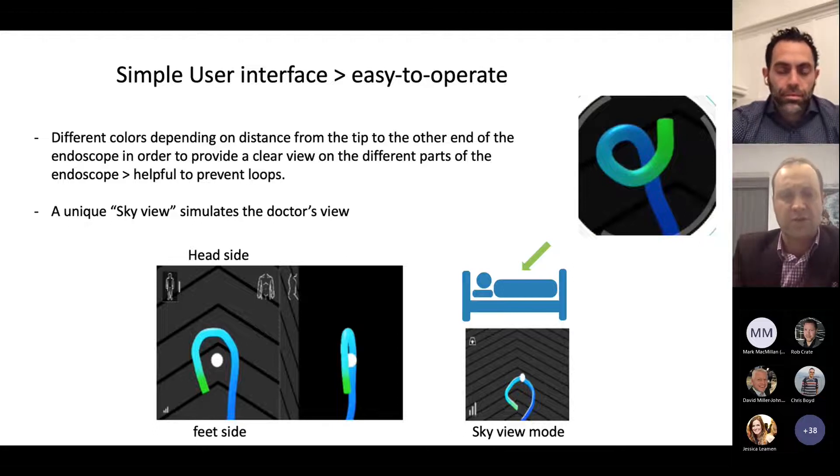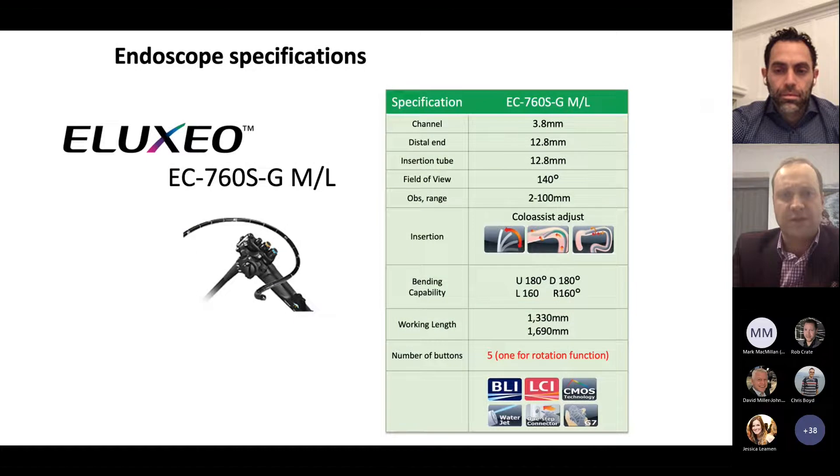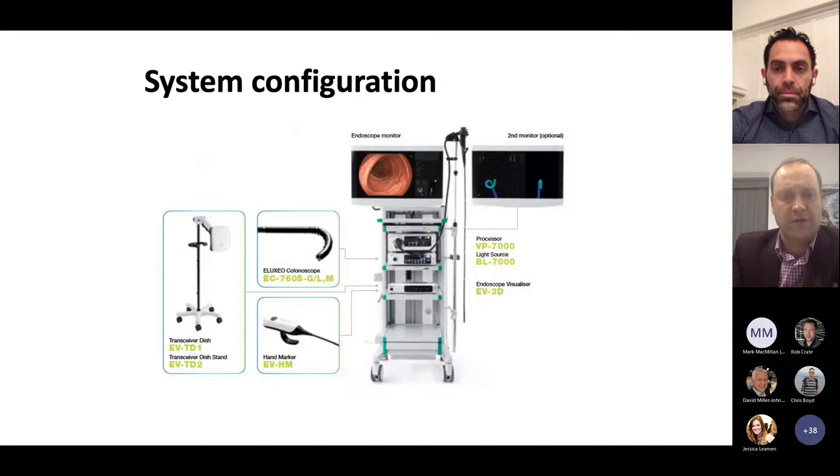There is a unique sky view mode in the bottom right corner, designed to simulate the position view from a bit further above the patient. These are the specifications of the endoscope — it's a special scope compatible from the Eluxeo series, 12.8 millimeters with a 3.8 millimeter working channel. In the room, you'll have the transceiver dish on a stand, the compatible colonoscope, the hand marker, and the rest stacked in your tower. You can have a second monitor, but it fits quite nicely onto the side of a standard monitor.